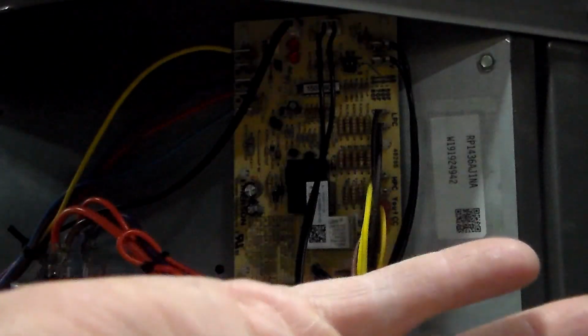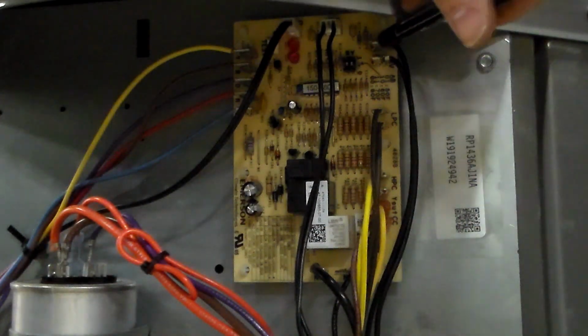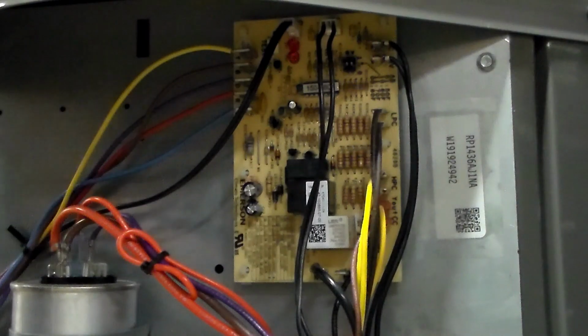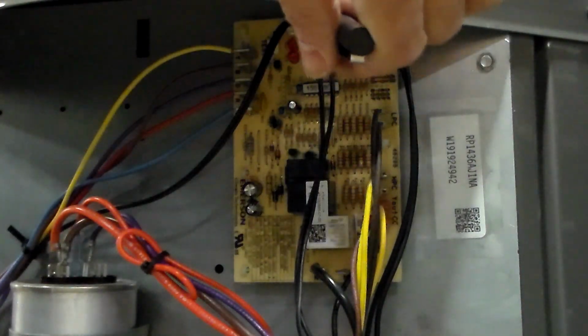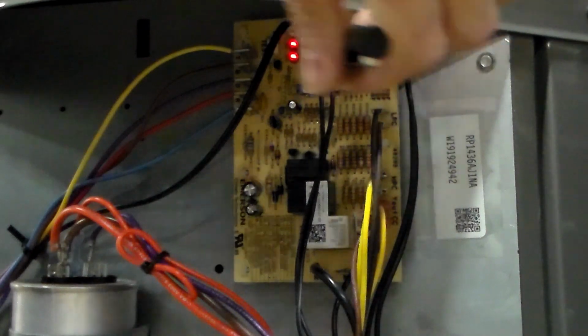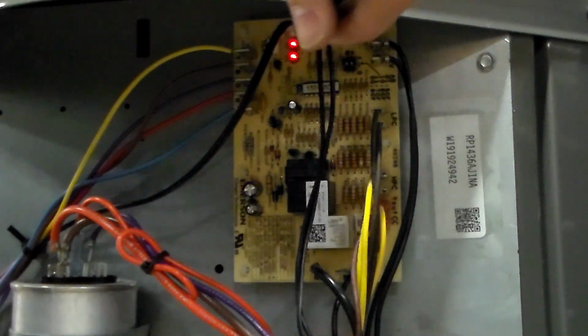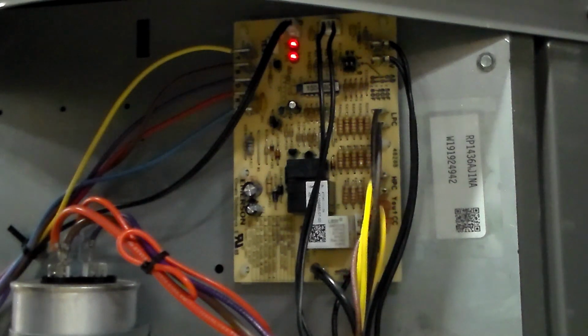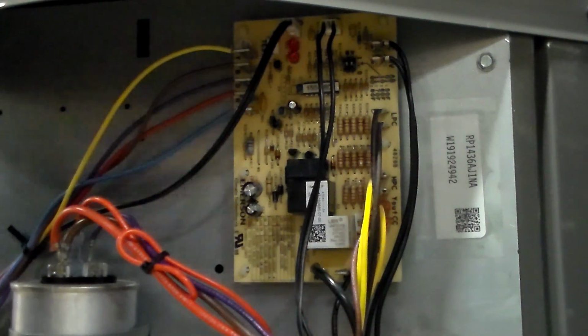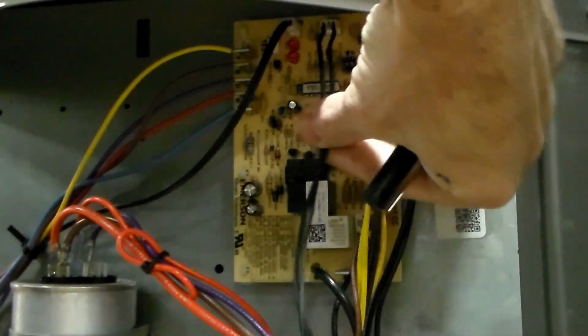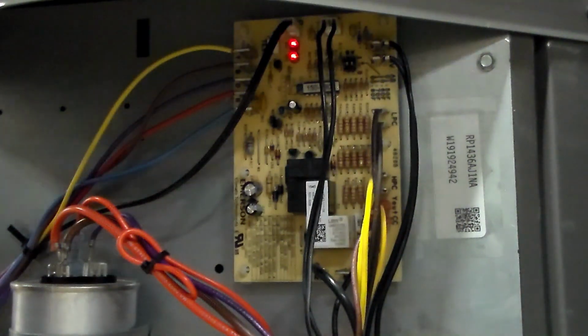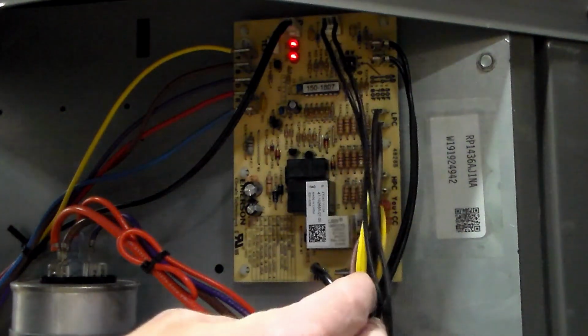Your high and low pressure switches, if you get those wires backwards, nothing you can go wrong there. Reversing valve, same thing. If you get those backwards, nothing you can go wrong there. The only thing you can go wrong on, but you can't, is because these clips here are the two sensors. They only plug onto the board in a certain way. So you can't put them on backwards, but they're designed to only clip on one way, unless you rip on them like some students did, and then you make it all dislodged and crappy. But aside from that, good to go.